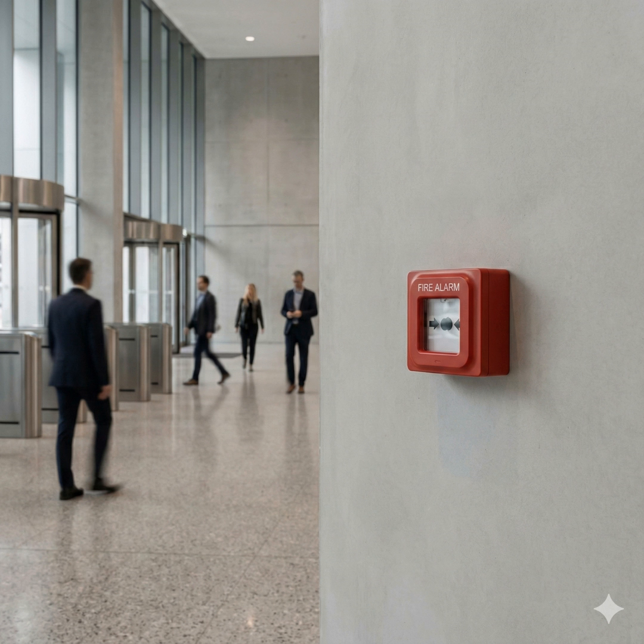So if they're the workhorses, what ensures they stay reliable over time? They must get dirty. They do, and that brings us back to those crucial standards governed by UL 268, which mandates something called drift compensation. Drift compensation. It's arguably the most essential operational security feature of a modern sensor. Think of the chamber like an odometer that slowly accumulates dust. That contamination gradually changes how light behaves in the chamber, making the sensor either too sensitive or worse, dangerously desensitized. Drift compensation algorithms continuously track the normal, clean baseline reading. As the chamber slowly gets dirty, the algorithm automatically adjusts the sensitivity threshold to keep the detector operating reliably.